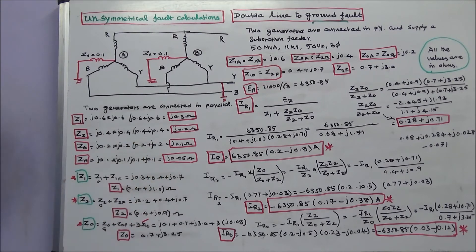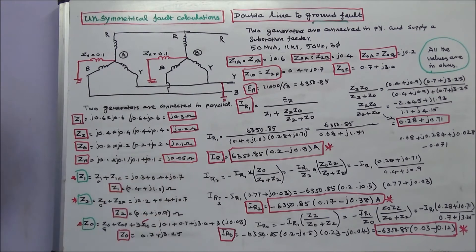The actual positive sequence, negative sequence, and zero sequence impedances are found by adding generator and feeder impedances. Z1 equals Z1G plus Z1F, giving Z1 equal to 0.4 plus J1.0 ohms. Z2 equals the negative sequence impedance of the generator plus that of the feeder, giving 0.4 plus J1.0 ohms. Zero sequence impedance equals the generator zero sequence plus feeder zero sequence plus 3 times Zn, where Zn equals J0.05. Substituting all values, Z0 equals 0.7 plus J8.25 ohms.